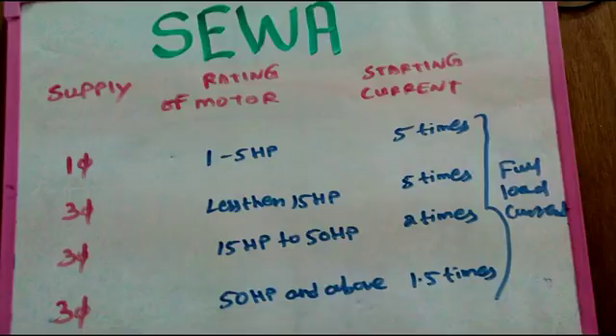This will be less than 15 HP, at 5 times full load current, so it will go above. If you have 15 HP to 50 HP in the 3 phase, it will be 2 times full load current. If you have 50 or above 50, it will be 1.5 times full load current.